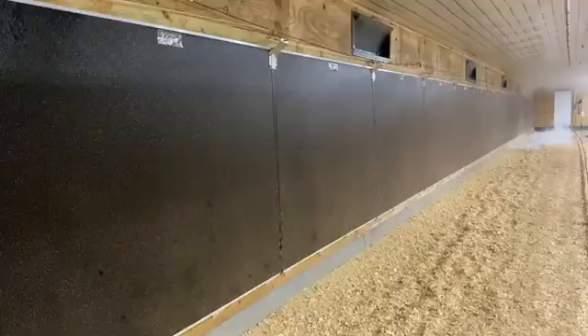It comes in through the cracks, falls to the floor, and forms a blanket of cold air across the floor. We're not utilizing the hot air next to the ceiling because the air is not coming in through the inlets. So the tighter we make the house, the more air that enters through the inlets, the more air that we're bringing in that's going to be warm and dried before it moves down to bird level.